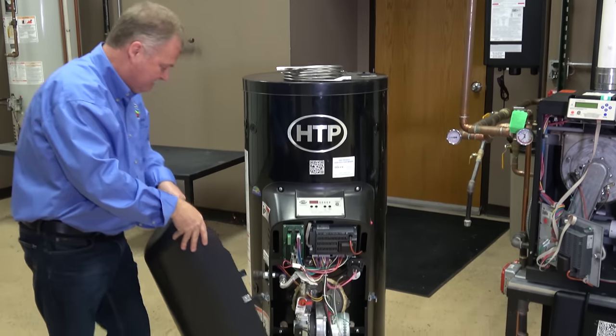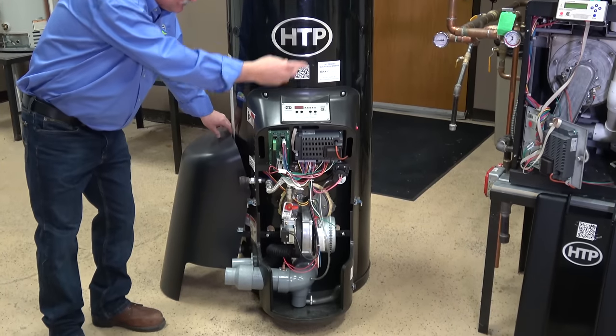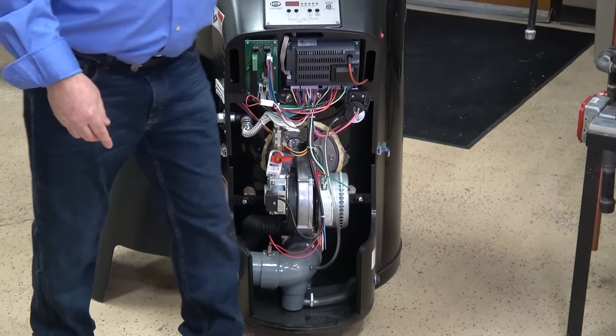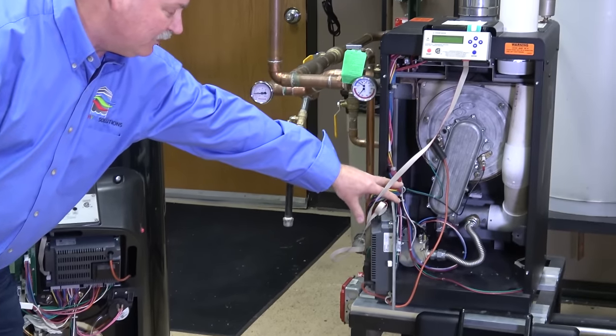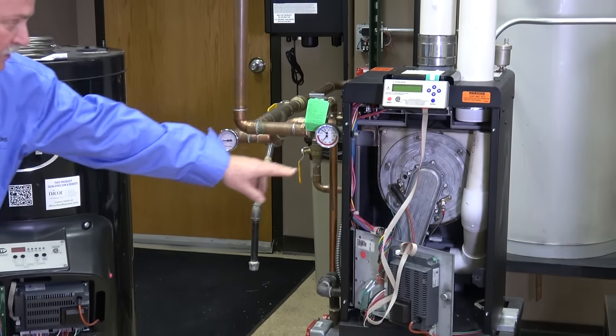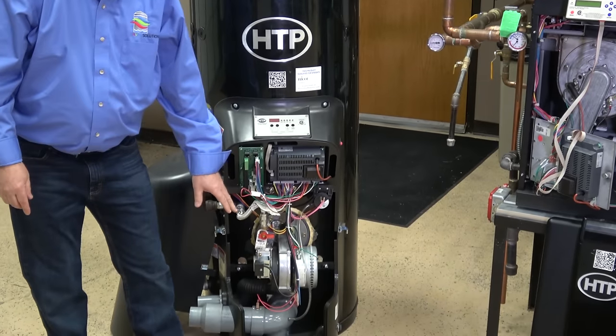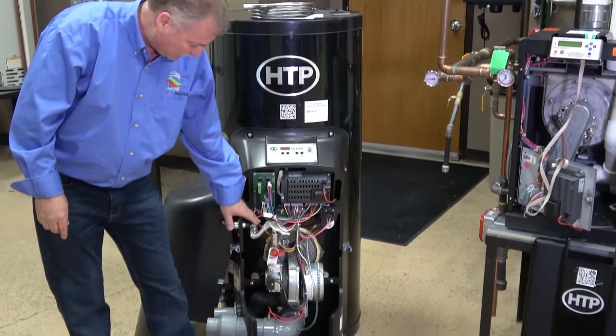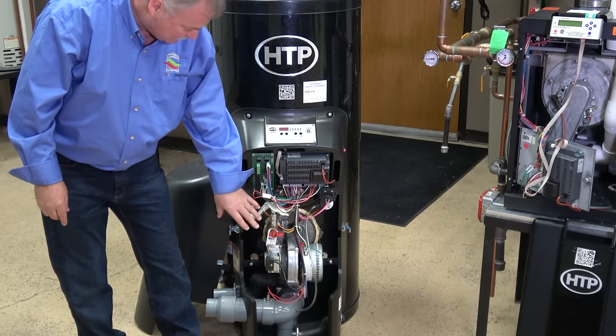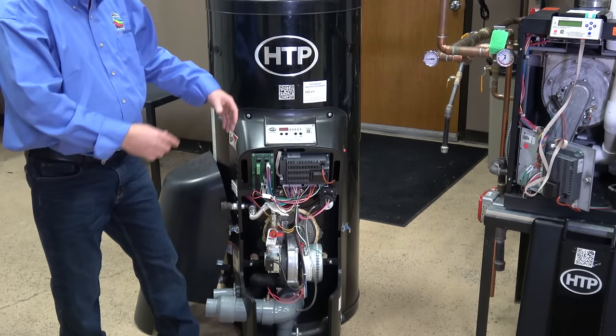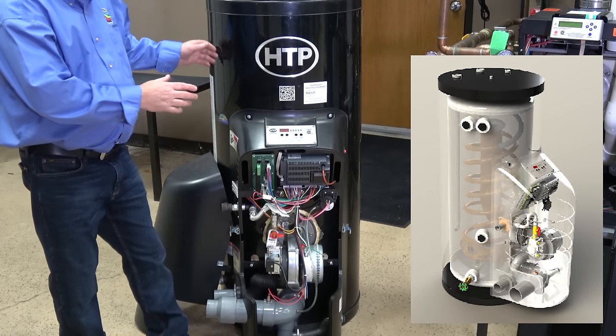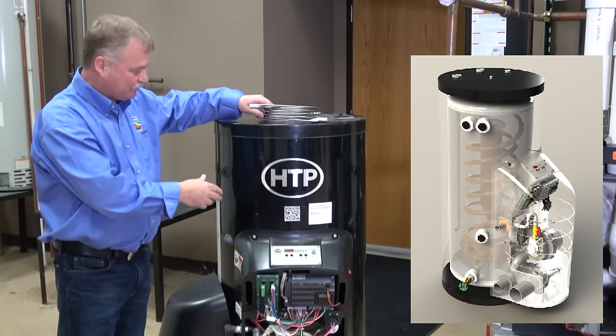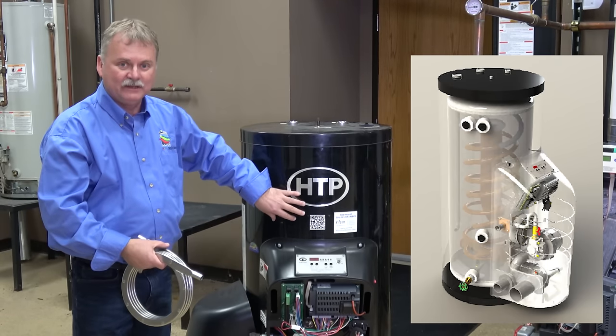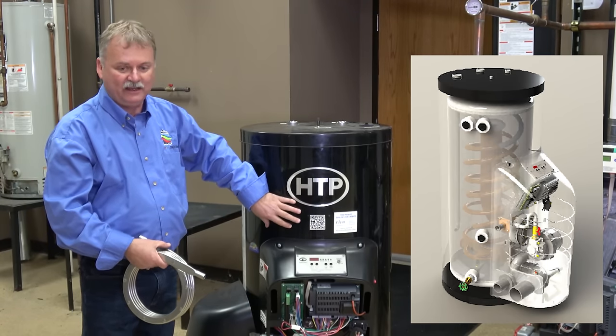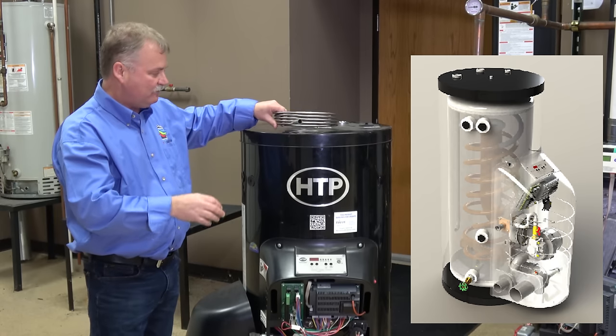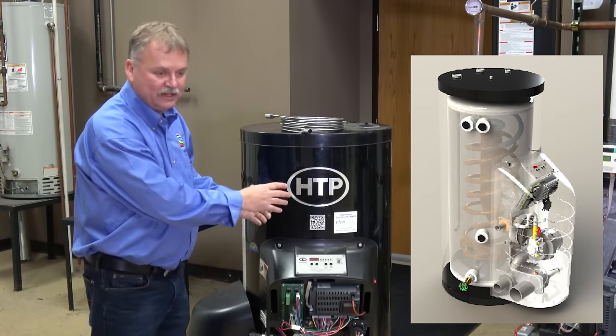If you look on the front, this looks very similar to the other unit over here. Okay, we've got the gas valve, everything else down there. We have a blower motor. We shoot in the tube. Same thing we have here. We've got our blower motor, we've got our high efficiency gas valves, everything else blowing into, and inside here is a big tube. But as you can see, this is a big tank, and it is. This is a 55-gallon tank, which has a very large 4-inch heat exchanger that comes up through the tank.